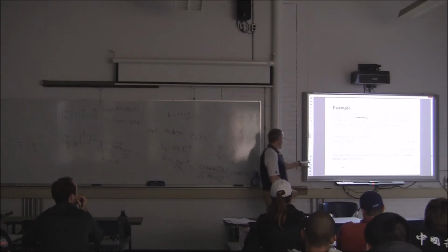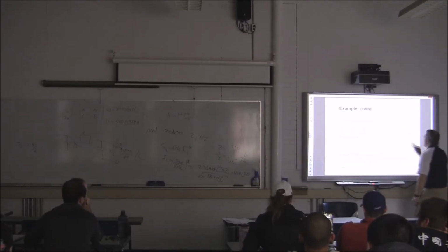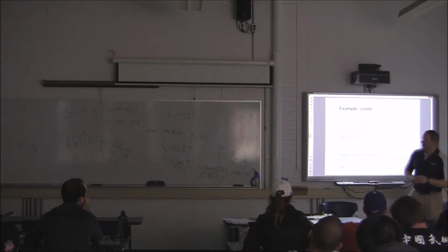Okay? We've already done the power triangle stuff. We know the current. Now we can go ahead and plug and chug. So these are our parameters. And what I end up with is a sending end voltage of 199.19 and a sending end current of 421.13. Well, anybody have any problems with that?